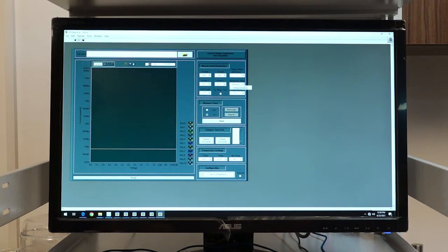We can also select wide range of integration times. For fast measurements, we'll select short. For the normal time scale measurements, we'll select medium. And if we are looking at lower currents where noise can creep into the measurements, we will use long sensitive mode. Along with these, we could also require giving optical excitations. For that, we will use the current. We will use this current fed to the LED as the factor for controlling LED intensity. And the total time that we allot for this measurement is given by this time unit.